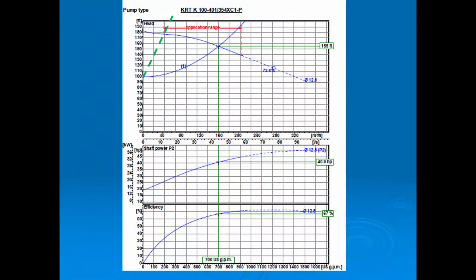So we go to our computer, we plug it in, and we end up with several curves. The first curve we have starts at 100 feet. Why does it start at 100 feet? Let me see, is there a pointer on this thing too? I don't know. So why does it start at 100 feet? If we put a pressure gauge on that pump, why does it start at 100 feet? That is our static head.